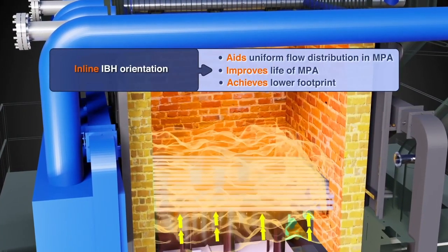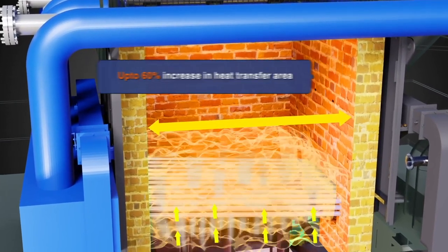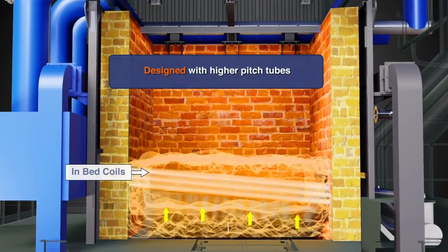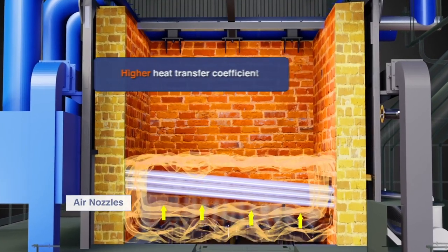In-bed Header Assembly: Transfers heat from the fuel bed to circulating water to maintain bed temperature, thereby minimizing clinker formation and lowering NOx. In-bed coils exhibit particle convection phenomenon which helps achieve far higher heat transfer coefficient compared to convection and radiation.